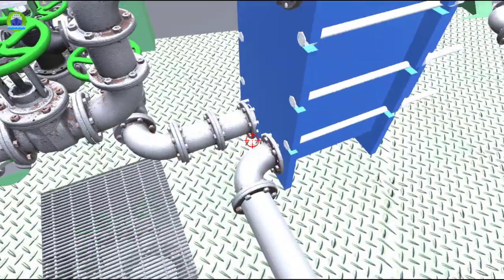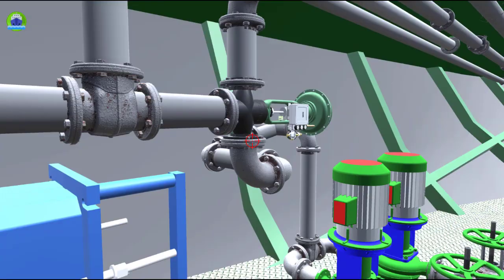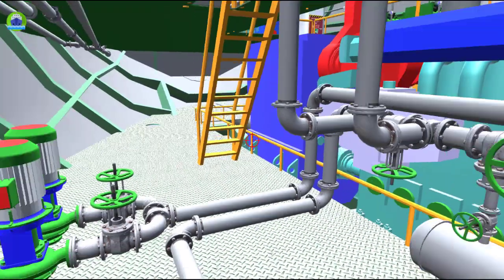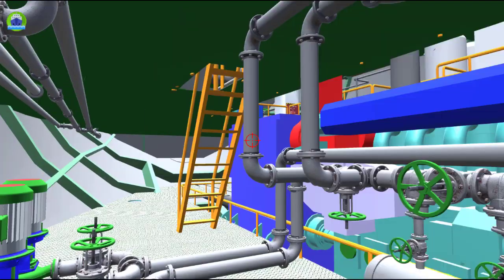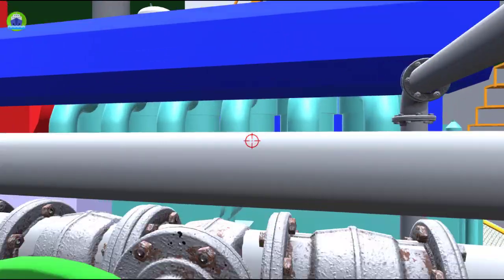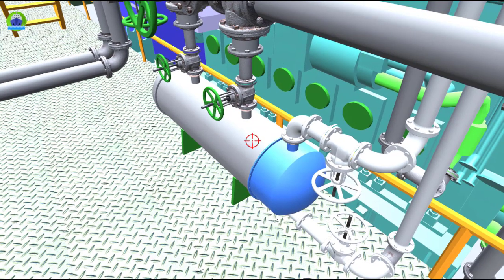The heat drawn out from the engine through the closed-loop circuit of the fresh water system is extracted or rejected by the seawater on the other side. This side is the low temperature and this is the high temperature. We'll have another discussion of the seawater system in the next episode. That's basically the virtual reality tour showing the actual layout, which may differ depending on the ship. You can also see the heater here — as mentioned, if the vessel is alongside in port and the engine is not running, a certain temperature is maintained.